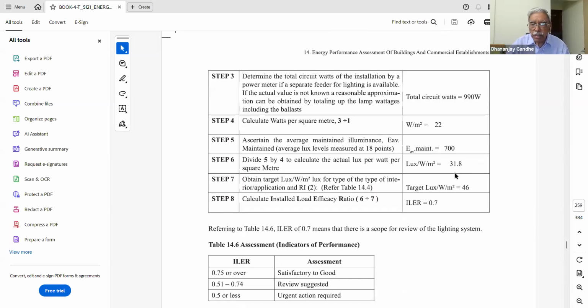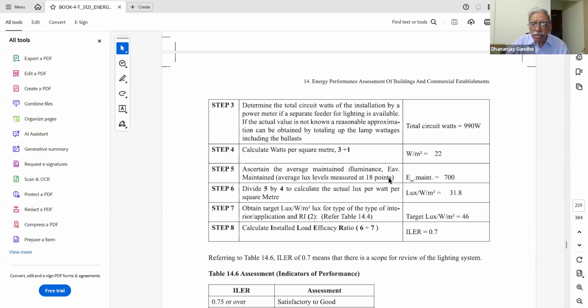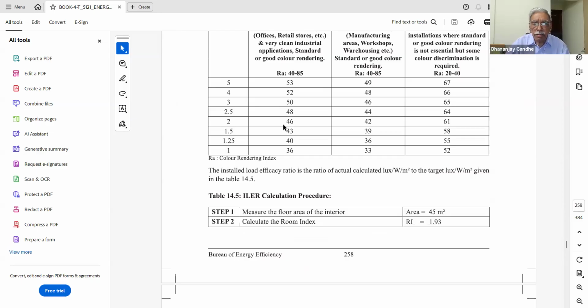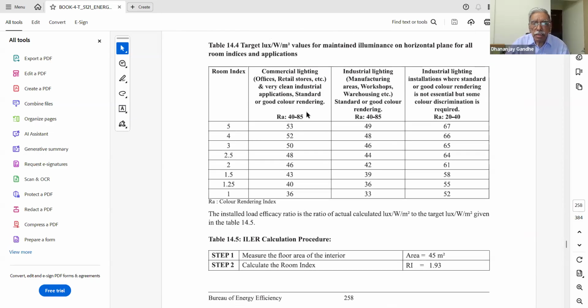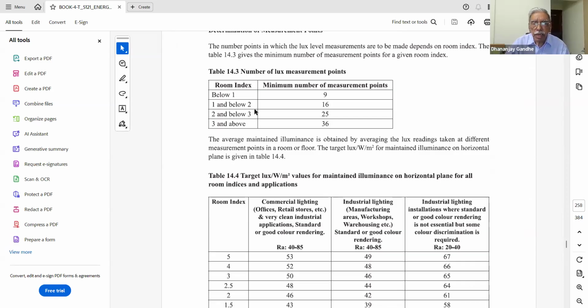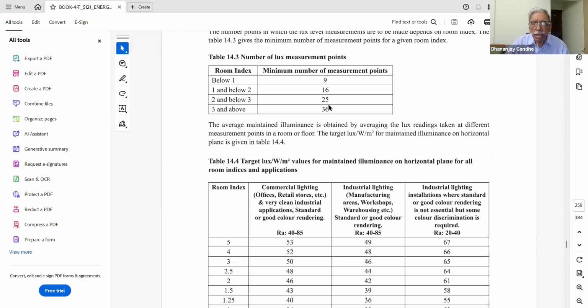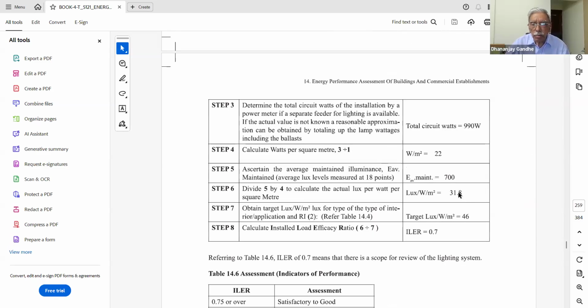The target level is 46, whereas the actual illumination is measured at these 18 points, as per this table for 1.93. So the average illumination worked out to 700. At 700, that is the actual measurement. What is specified, watts per m square, is 22. You divide 700 by 22, so it gives the actual lux level per watt. It goes as 700 by 22 is 31.8.